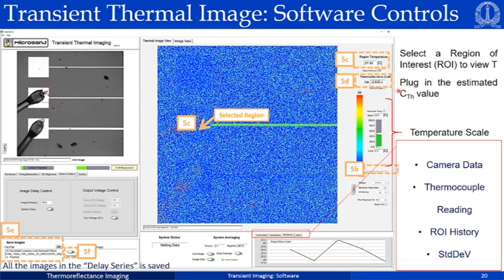If this number is wrongly typed, or you have forgotten to type the number, then this would show an arbitrary temperature value which will not be correct. So for monitoring in this window, you have to select a thermo-reflectance coefficient value that you have measured.